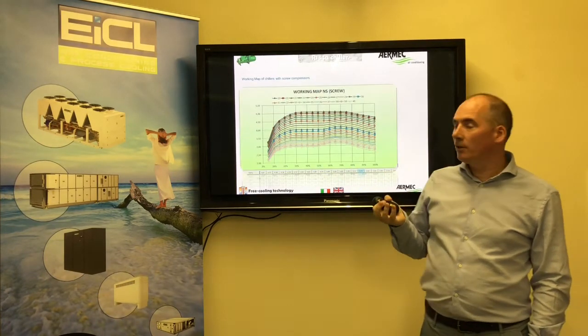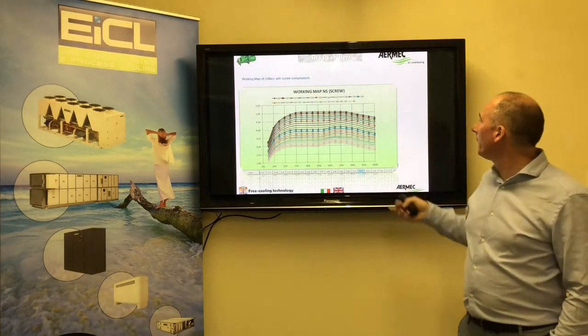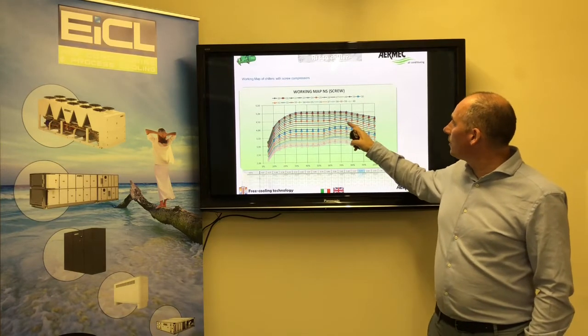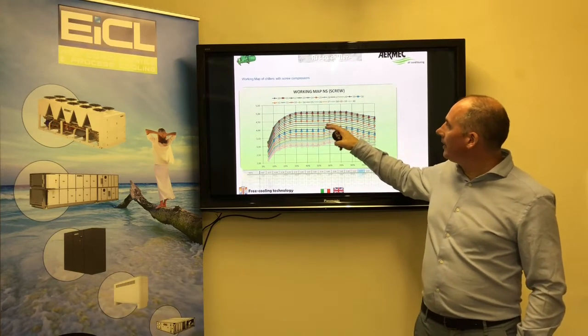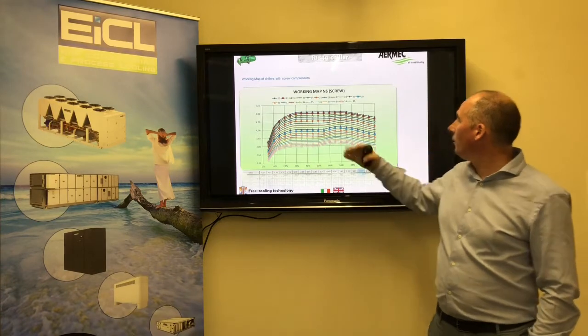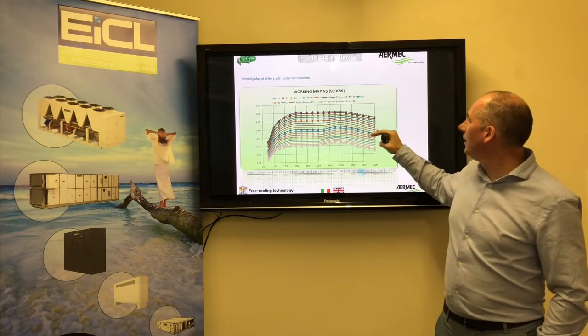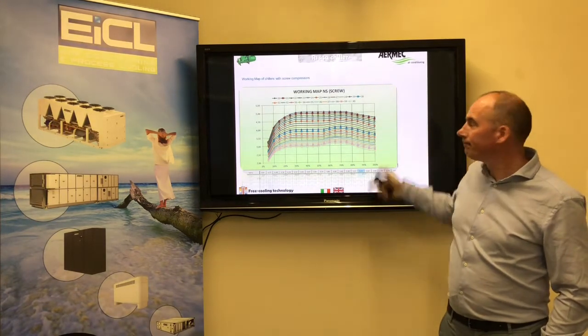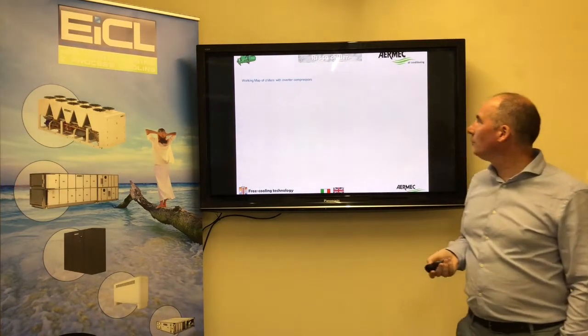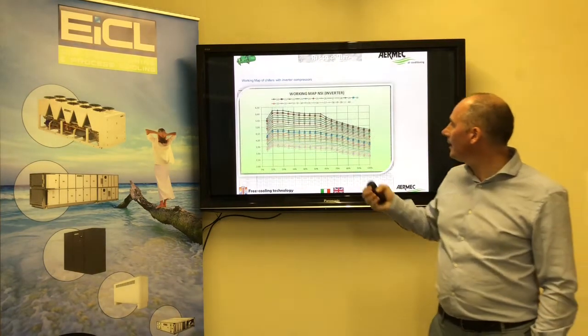So this is the non-inverter screw compressor first of all. You can see the efficiency goes up as well. It seems to drop off a little bit, level off, and then drops off at the end. But again, in general, the efficiency is better in part load than up at 100%. Again, we can compare this with the inverter screw.